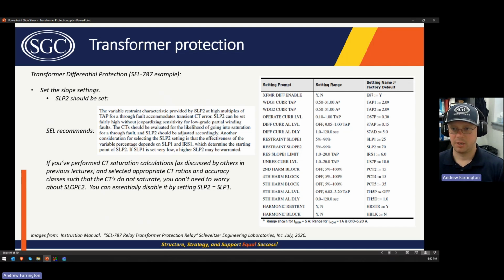They don't know if it's crushed, but they know that the existing conductors work. They just want to put the new relay in the same spot, reconnect the same CT cables. But you look at them and you go, oh, okay, it's going to saturate. It's a really long run, and the CTs are going to saturate for fault current. Well, now you need to look at this, right?